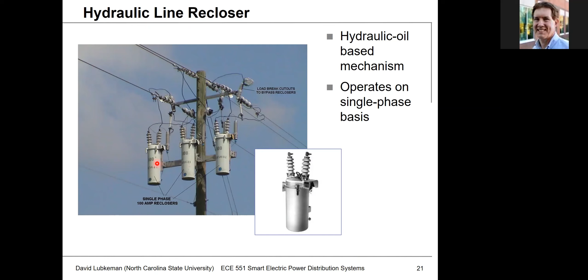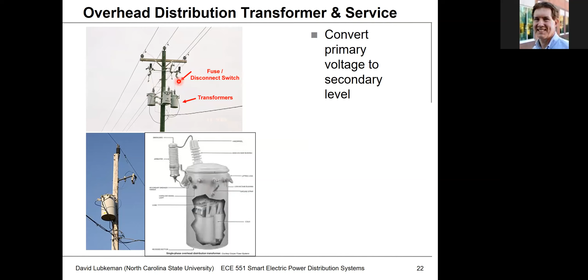When we get closer to the customer, we have to step the voltage down using a customer distribution transformer. These could be mounted up on the pole, or located near the ground, but a lot of times they're mounted up on poles. This is the standard transformer you've probably seen before in other power systems classes. Note that you mostly have to provide protection with these devices. You could have self-protecting devices, but a lot of times you have to add a fuse or a surge arrestor when you mount these out into the field.